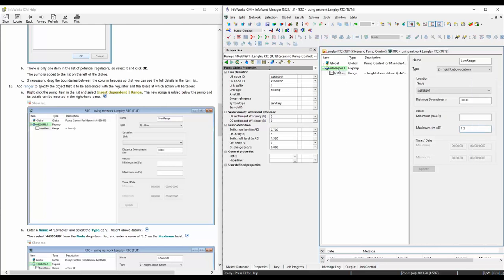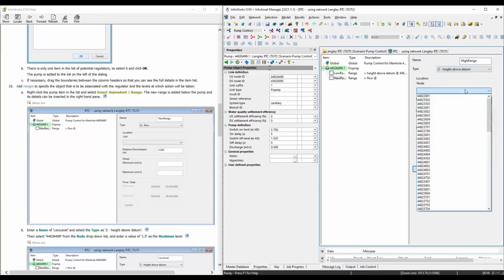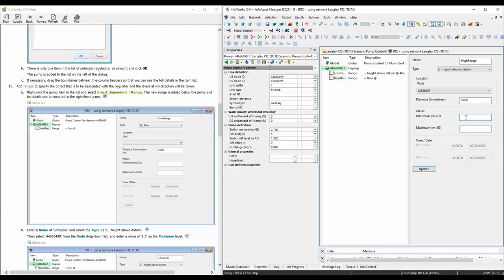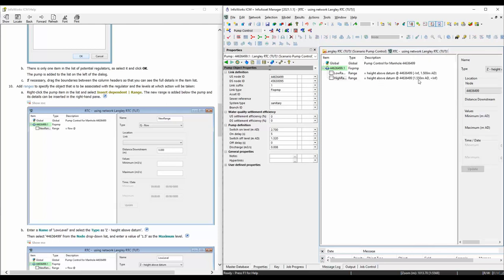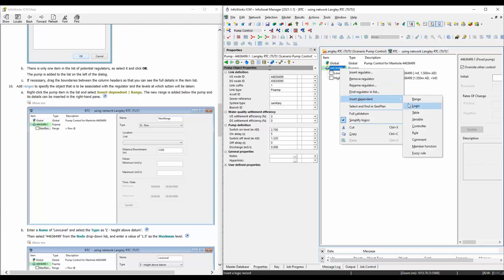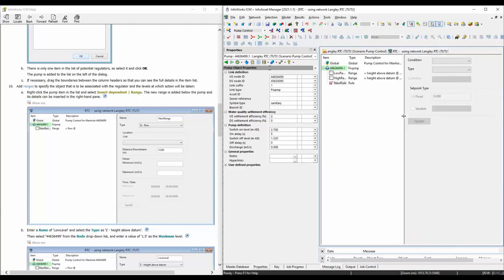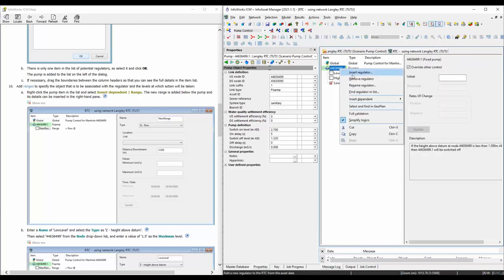Now add the high range - same setup. Call it 'high range', type Z again, same node ID 44636499. For this one, because we want from 1.55 to infinity, enter 1.55 as the lower bound. That's the high range - once it's above this we want to turn the pump on. Next, to add the rules, right-click and insert dependent rule. For the low range rule, set the condition to 'low range' and set the action to switch off. Hit Update - you can see it's switch off.